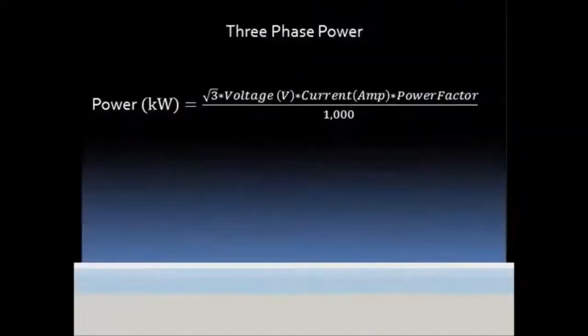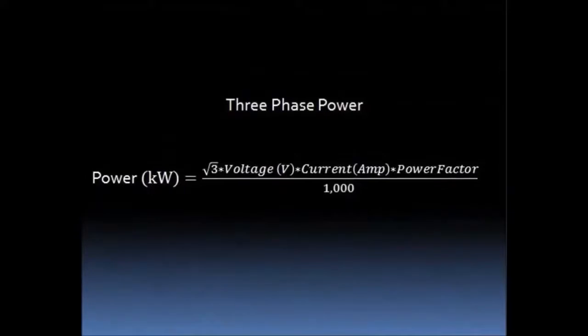Take the average of all amperage readings and all voltage readings to get your final measurement. To determine power in kilowatts, multiply the square root of three, voltage in volts, current in amps, and power factor. Then divide by a thousand to convert.